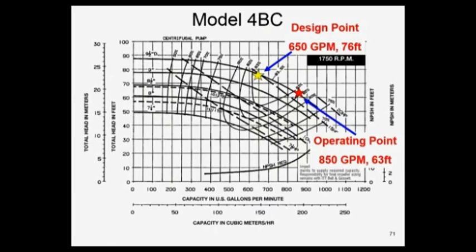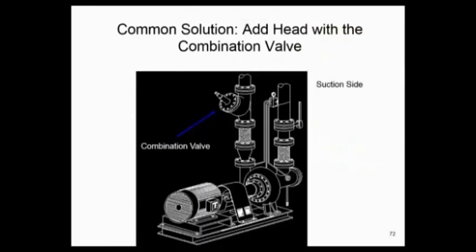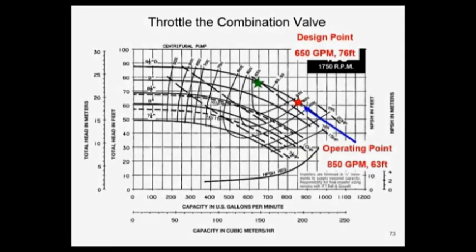How would you balance the system? What's involved? A common solution to this would be to go to that triple duty valve, a combination valve, and throttle back on it to force the head back up to 76 feet, and force it back to the required flow rate of 650 GPM. Let's see what that looks like. Red is where we're running, the green is where we want to wind up at, flow-wise. Now we could throttle the triple duty valve or throttle the balancing valve, and I've added pressure drop to the system, I've changed my system curve.